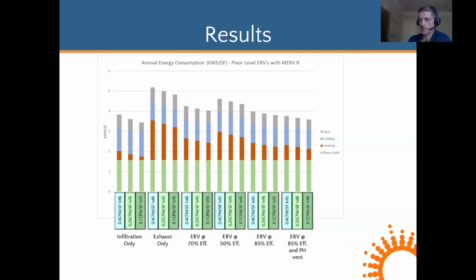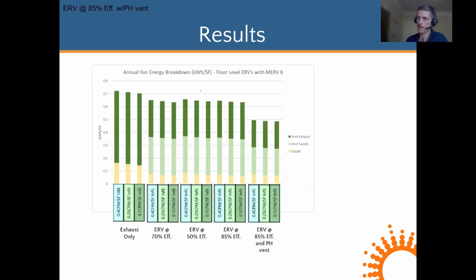And as we change the effectiveness of the ERVs, the heating energy changes, the cooling changes a little bit. So we wanted to just compare the fan power explicitly. So looking at just a fan power comparison here, we can see that the ERV units have exhaust and supply fan power, and that total fan power is a little bit higher than just the exhaust, which makes sense because we have 2 fans instead of just 1 versus the exhaust only. There's also a higher static pressure to overcome with the heat exchangers.